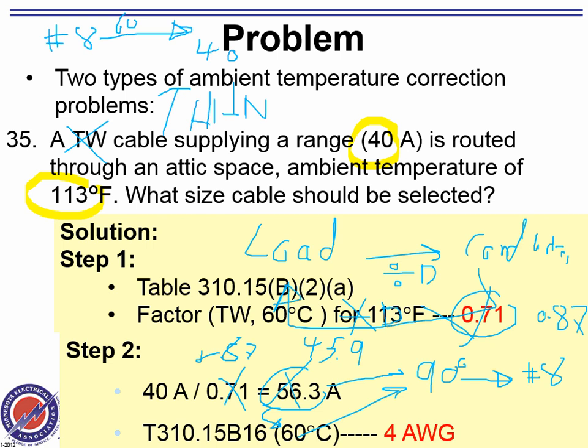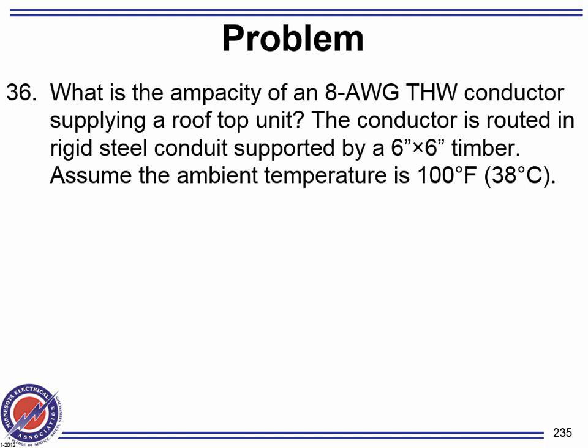You see that? 10, for example. Say I came up with a point. All right, what's the ampacity of number 8 THW supplying a rooftop, and we have a distance from the roof of this, and the conductor is this type. Remember, pay attention to the type of this conductor. And here's the ambient temperature.